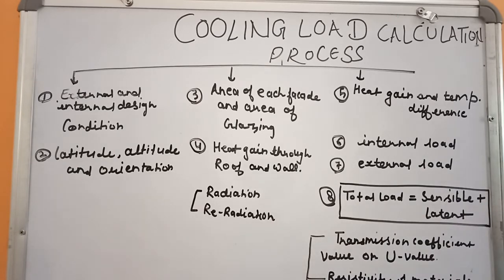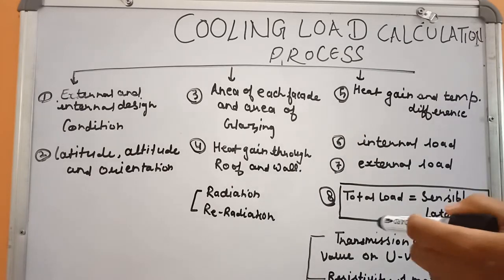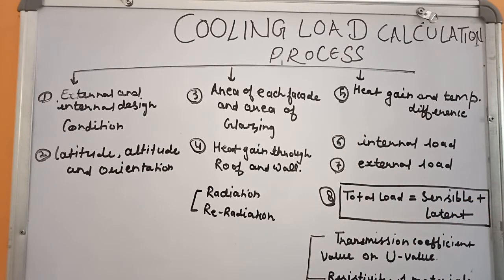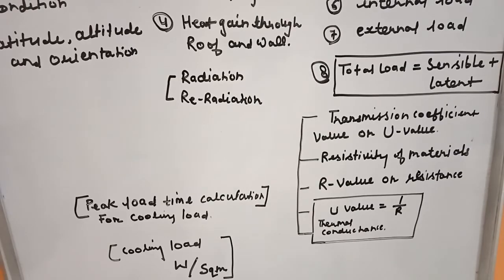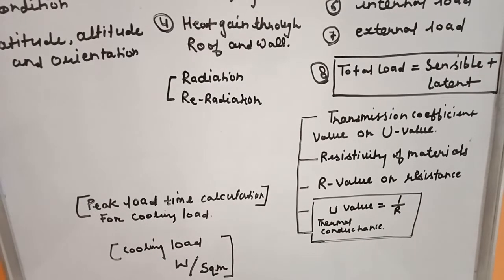So sensible heat, which we sense directly, or which is a heat gain through direct heat gain from outside, plus latent, and latent is through people, through objects. So we calculate this as data from outside temperature, inside temperature, and we get our sensible plus latent heat. Then we consider transmission coefficient value or U value of material, like U value of wall, U value of window. Then resistivity of material, which type of construction is that, which type of material we are using in building, that has some resistivity.